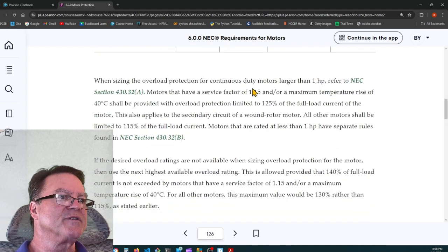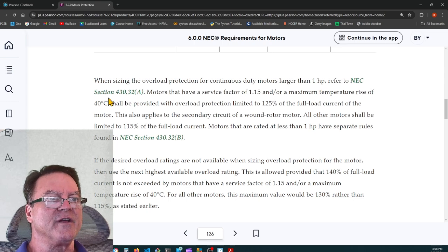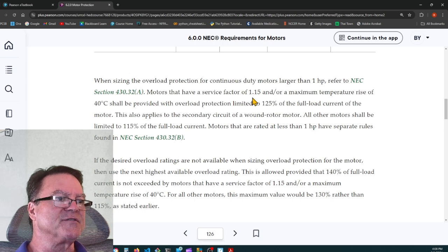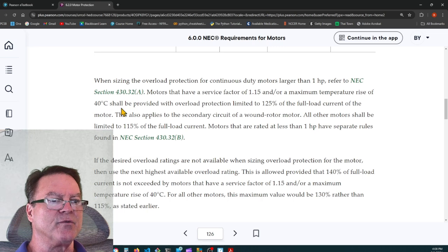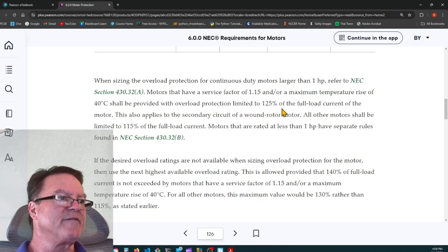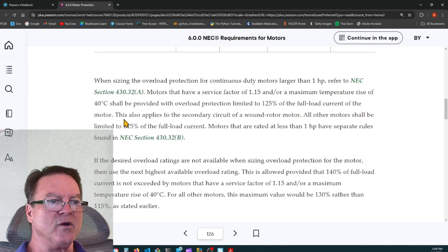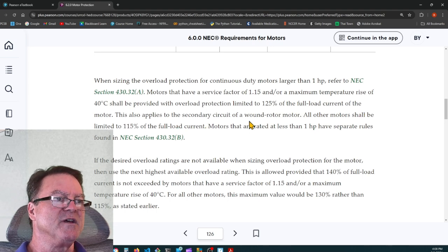When sizing the overload protection for continuous duty motors larger than 1 horsepower, refer to NEC section 430.32A. Motors that have a service factor of 1.15 and/or a maximum temperature rise of 40 degrees Celsius shall be provided with overload protection limited to 125% of the full load current of the motor. This also applies to the secondary circuit of wound rotor motors. All other motors shall be limited to 115% of the full load current.